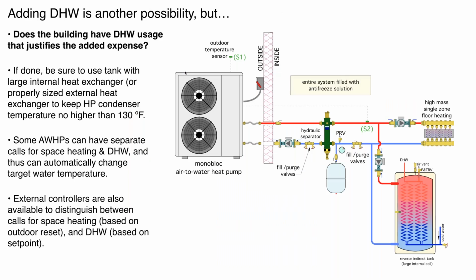Now, domestic water is another possibility, and I'm just showing a reverse indirect tank here, basically in parallel with the circulator and the high mass distribution system. And some of the heat pumps today do have the controls where you can call for domestic water heating separate from space heating. And all that does is allow the heat pump to target a higher temperature.